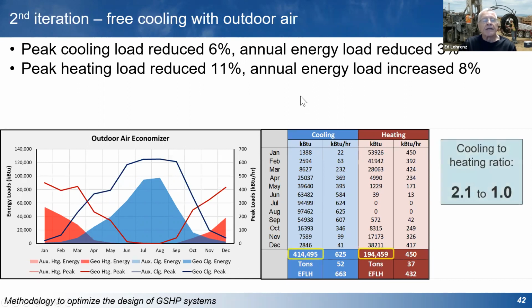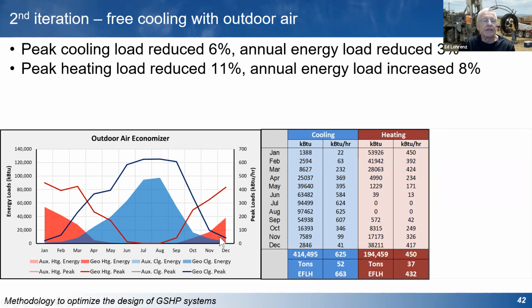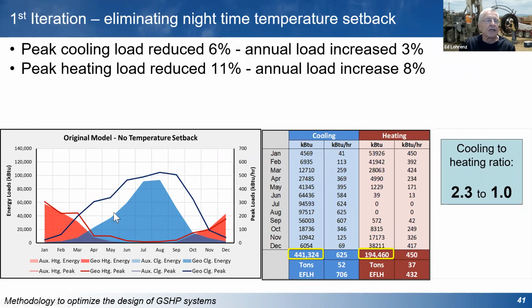In the next iteration of the energy model, basically taking advantage of outdoor air to cool a building, an outdoor air economizer, what that does is reduce the amount of energy that we're going to have to reject to the ground, 414,000 kBTUs annually. It doesn't change the peak very much, but it does change the amount of energy that we're rejecting to the ground. You can see the difference on here, there's a slightly larger cooling load annually than there is heating load.